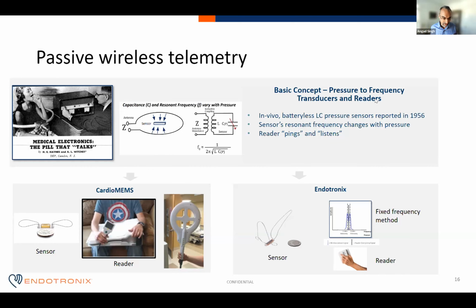So you have the basic concept, but there are a lot of engineering details that you have to go through to get to the real world implementation that takes millions of dollars and many years. But that's what they use. They use this building block and really made it work in a reliable fashion for a daily use product. And so what happens is the implantable sensor has the LC circuit in it. It's constructed using MEMS technology, and it makes a very small package that gets implanted. On the outside, you have a pillow that is a reader with a coil in it as well, that then pings and listens to the signal. So you can ping it and listen to it. So it's almost like striking a guitar string. It rings down and you listen to it, and you repeat this more than 1,000 times a second to get a really high fidelity pressure waveform from inside the body.